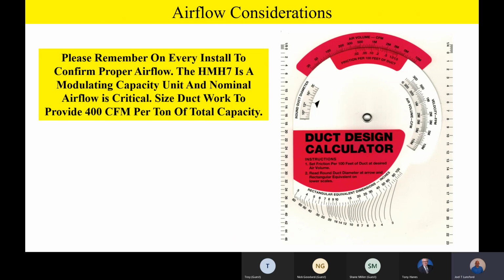The evaporator starts getting cold, maybe even starts wanting to ice up a little bit. Well, the system outside is going to sense that through all of its sensors, and it's going to start reducing capacity because it sees that there's a reduction of capacity inside because the suction pressure is coming down, the liquid pressure is coming down, superheat's coming down. You cats get the idea. So the modulating unit, its reaction to poor airflow is to screw capacity down. Well, if you've got bad airflow and it's hot outside, the unit is going to sit here and try to compensate for that. But the only way it's going to compensate for that icing up evaporator, because it's poor airflow, guess what? It's going to modulate down. So I just can't stress that enough. Airflow is really important, especially on modulating units, if you want them to operate properly and at their full capacity.